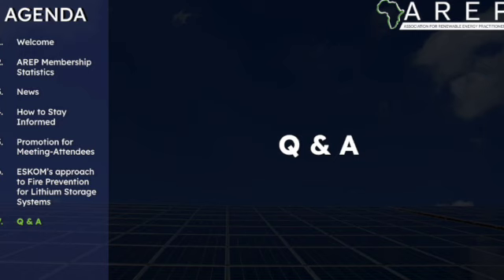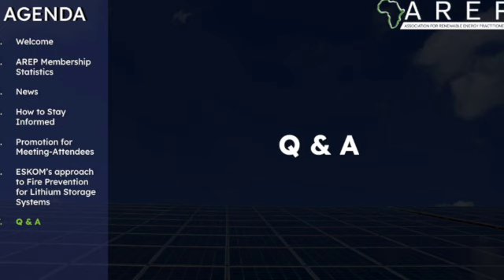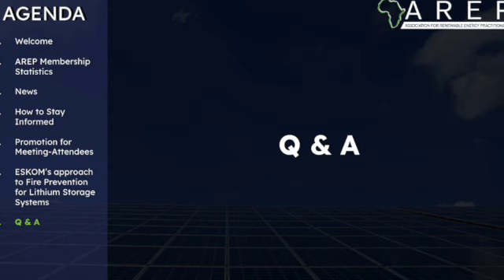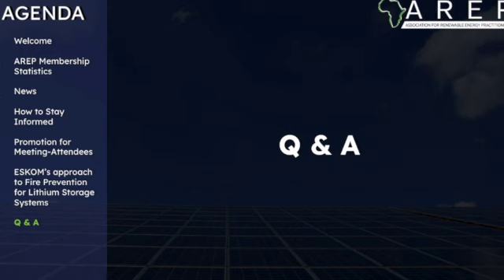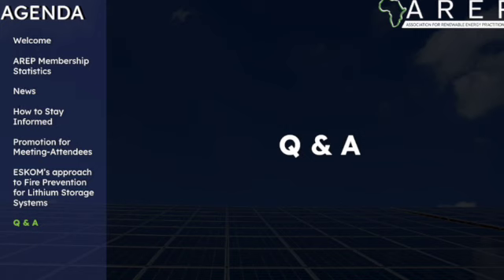I've got a research paper I can share where they've indicated that the fireball can only be used in very specific circumstances - mainly you have to have an enclosure, a tightly enclosed area, because basically that fireball is a DCP bomb. The dry chemical powder typically in a fire extinguisher is inside that ball, and when it explodes it throws all of the DCP powder in whatever direction the explosion takes it. So not a good thing for wide open spaces. They've tested it and I can share that paper.